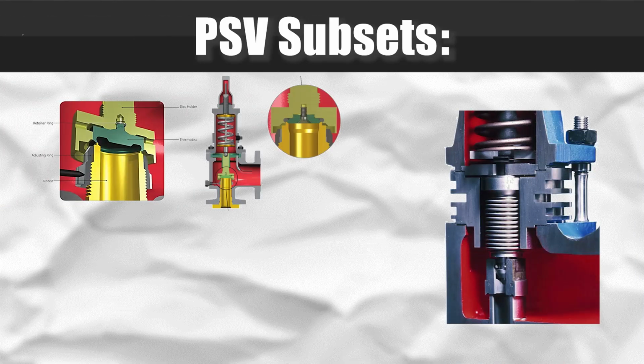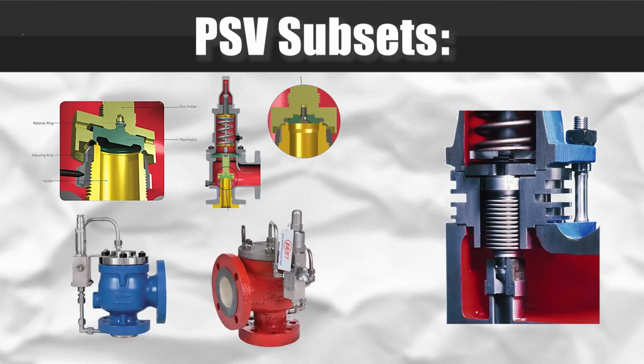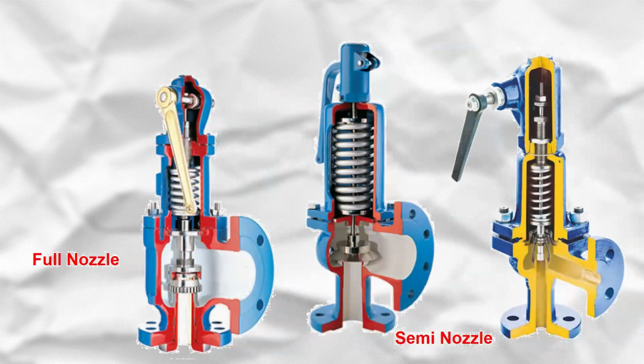The inlet size is always considered smaller than the outlet size. This valve is categorized into 3 subsets, which are conventional type, balanced bellows type, and pilot-operated one. One of the most important factors to select the appropriate type is back pressure amount. For instance, if back pressure is less than 10% of set point, conventional type is chosen. The PSV contains 2 main parts, body and the bonnet. The inlet nozzle could be categorized into semi and full nozzles. I personally recommend the full nozzle one because, as you can see, full nozzle can be extracted from the body, and in other words, it is changeable.